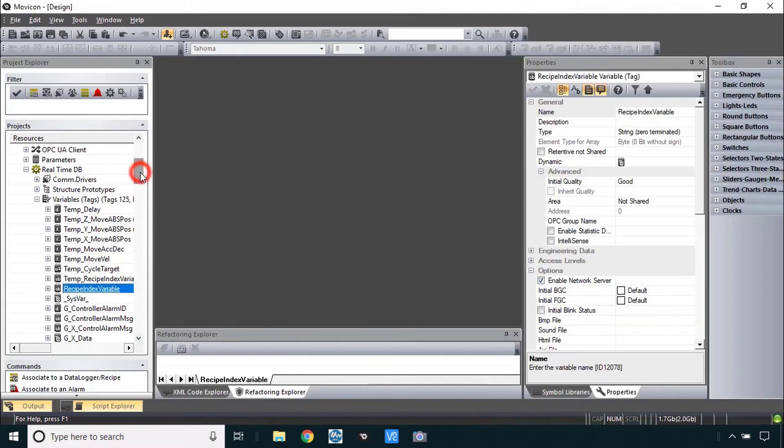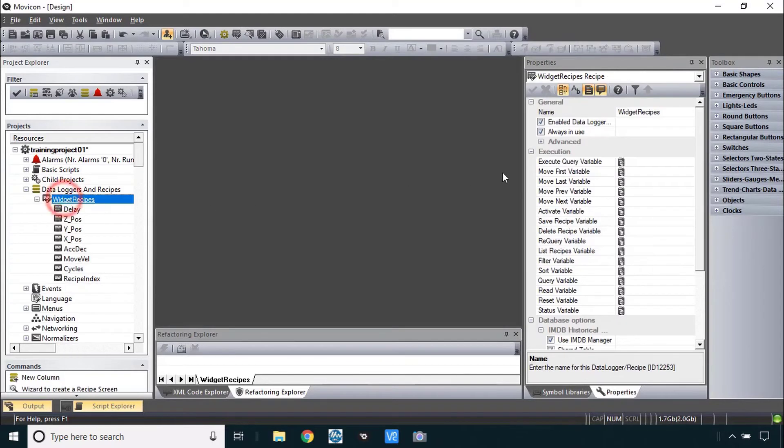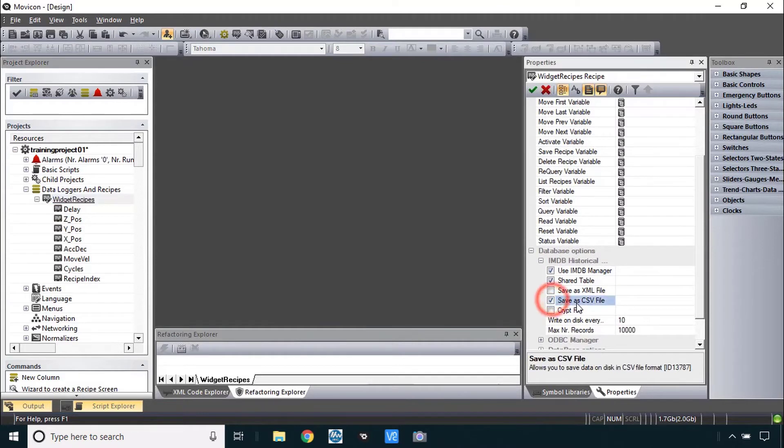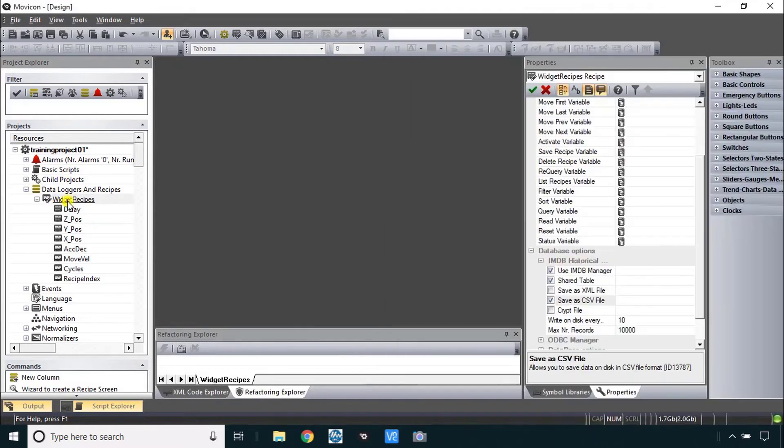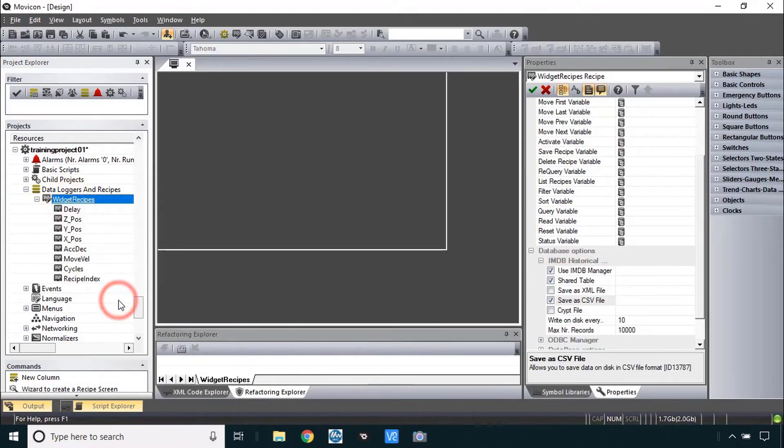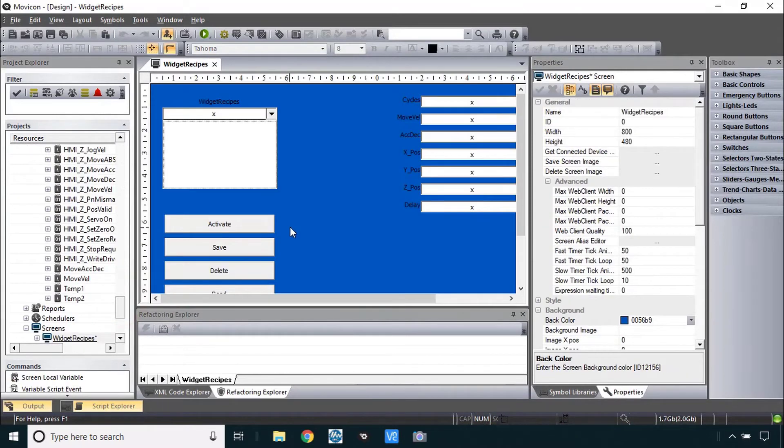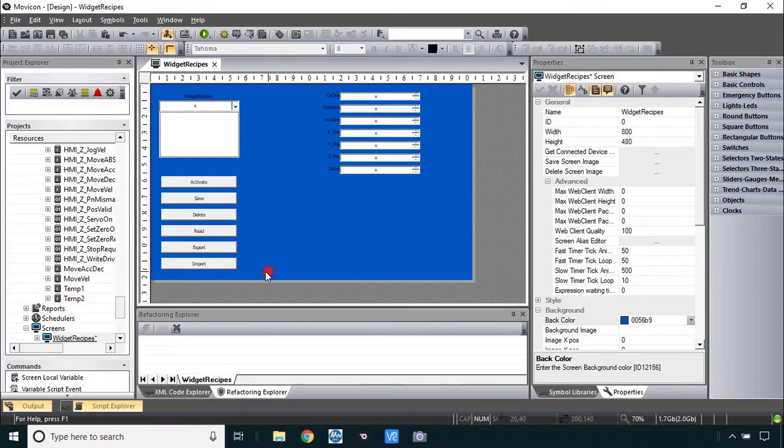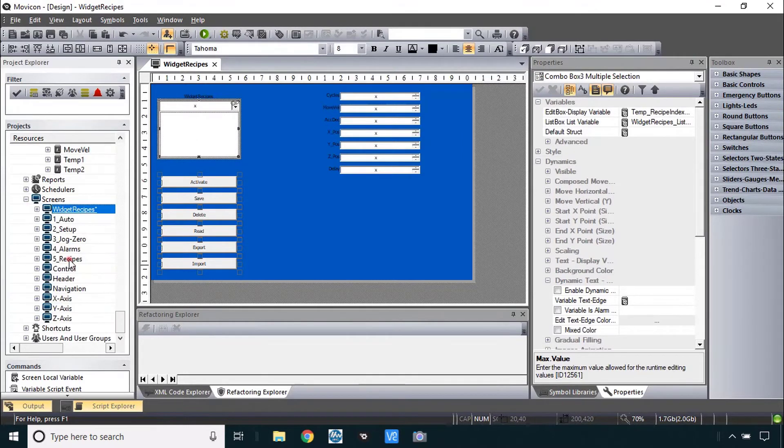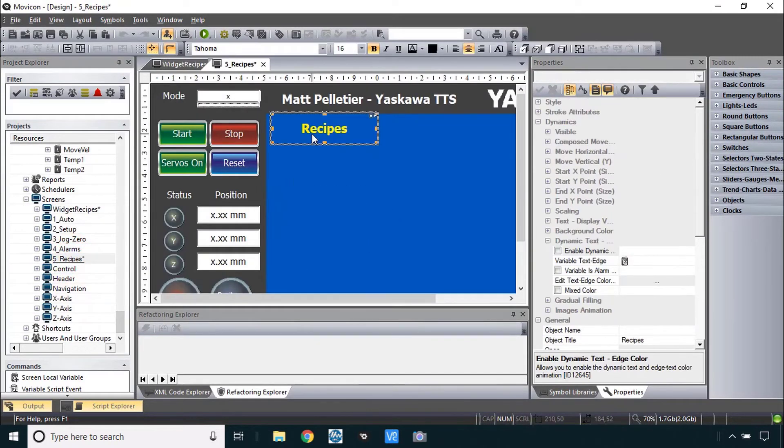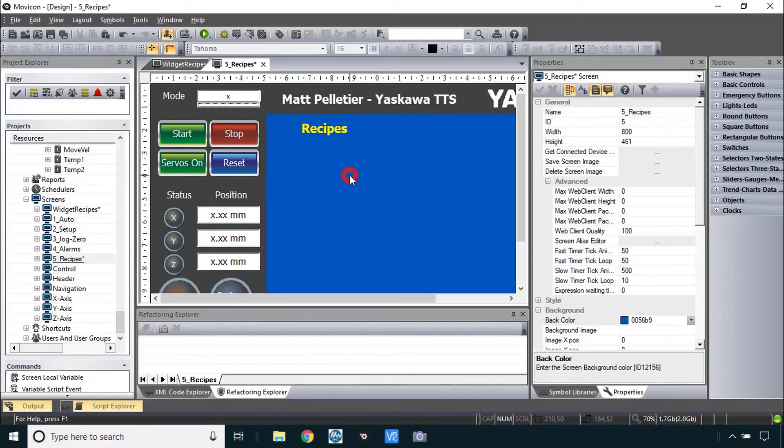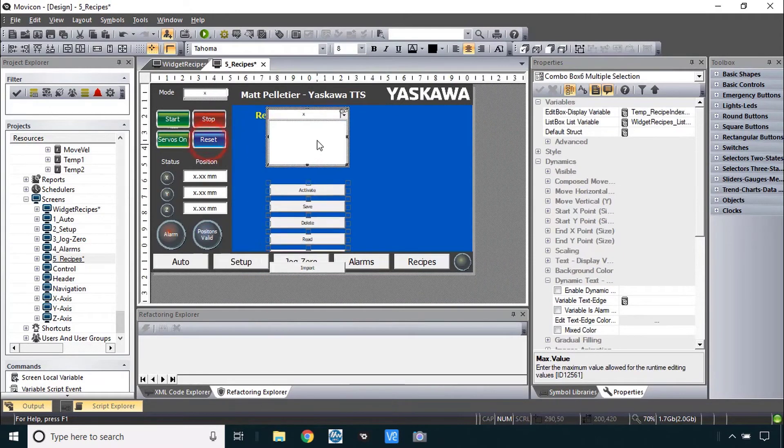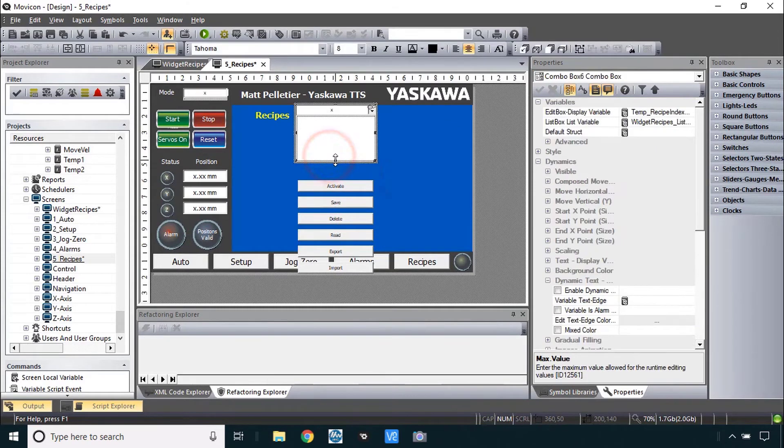Now it's time to create the screen and the first step here was to go to that recipe and check the property under database options called save as CSV file. You'll want that for the import and export function. And then right click to create that recipe screen. Create recipe screen. And like I said in the overview the only pieces I want from this are this combo box and these buttons. So I will select those here, copy and go to our prepared recipes screen. Maybe I'll use that as a title up here and paste this in.